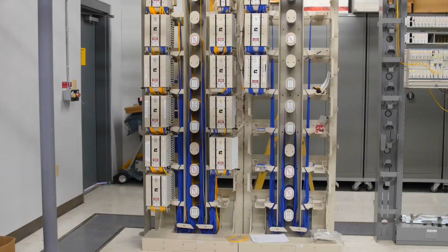When subsystems are installed in the wrong sequence, commissioning is delayed while prerequisite systems are made available. There is typically a very specific sequence that must be followed for startup, and construction deliverables must align with this for an efficient completion of the project.